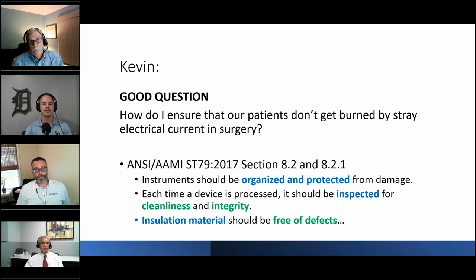So note here that it talks about organization and protection, which I thought was interesting. It talks about inspection for cleanliness and integrity, and it mentions insulation material being free of defects. Notice it didn't say anything about laparoscopic instruments only — any insulated instrument applies here, or even better, any instrument intended to be used with electrical current.